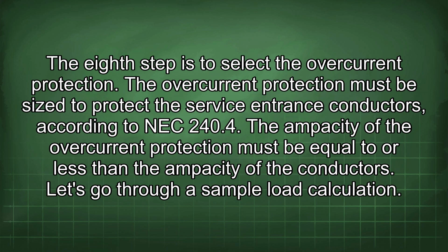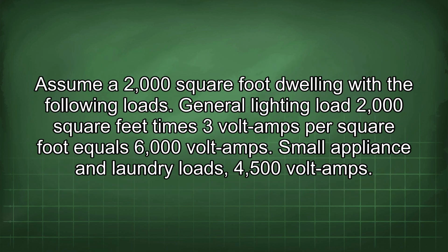The eighth step is to select the overcurrent protection. The overcurrent protection must be sized to protect the service entrance conductors according to NEC 240.4. The ampacity of the overcurrent protection must be equal to or less than the ampacity of the conductors. Let's go through a sample load calculation. Assume a 2000 square foot dwelling with the following loads. General lighting load: 2000 square feet times 3 volt amps per square foot equals 6000 volt amps.